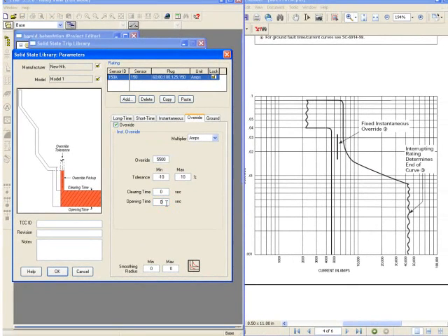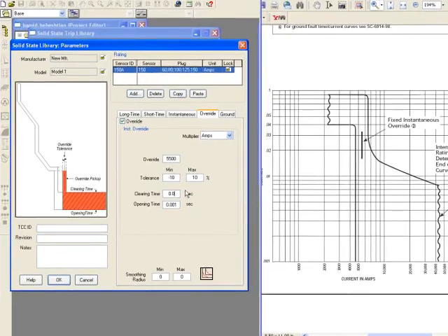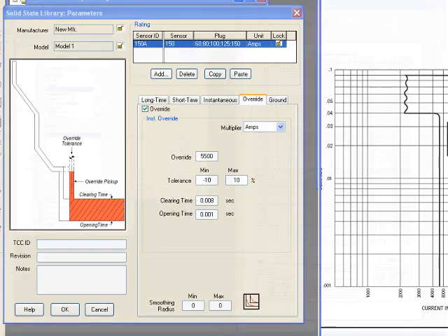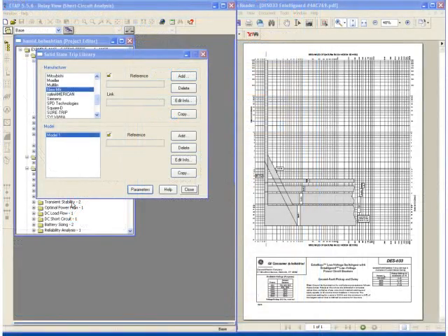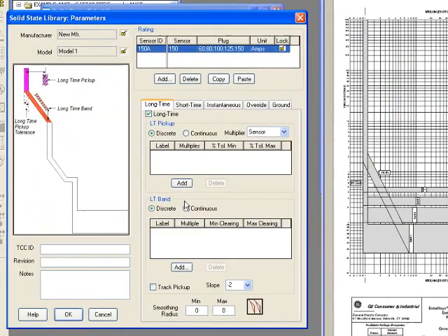If you want to go below the pickup value, you have to specify a negative sign, also for that clearing time, and the opening time is a fixed value. As you can see in this case, the opening time is .001 seconds, and the clearing time is .008 seconds.